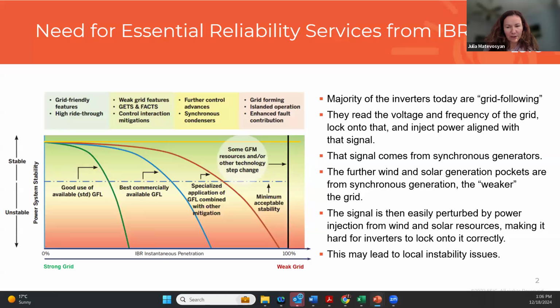So first, why are we talking about grid forming today, and why do we need it? The majority of inverter-based resources today—solar, storage, and wind—are so-called grid following. What they do is read the voltage and frequency of the grid, lock onto that signal, and inject power aligned with it. That grid signal comes from synchronous generators today, since the power system was designed historically around synchronous generator principles. The further wind and solar generation resources are from synchronous generators, the weaker the grid.